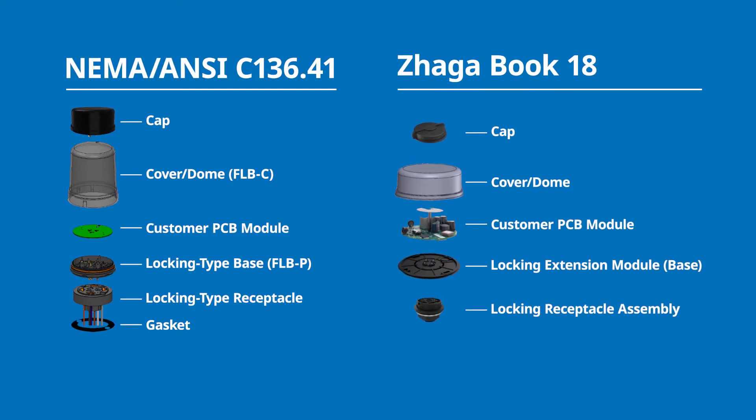There are a couple of levels in the product — a base, a receptacle, a dome, and a cap. Typically the receptacle brings power and sensing contacts. You also need gaskets to seal with the luminaire itself, and a dome or cap to cover the module handling all sensing activities. The total solution, whether NEMA or Zhaga Book 18, is going to be an IP66 rating — dust and moisture compliant — because street lights exist 10, 20, 30 years out in the elements.